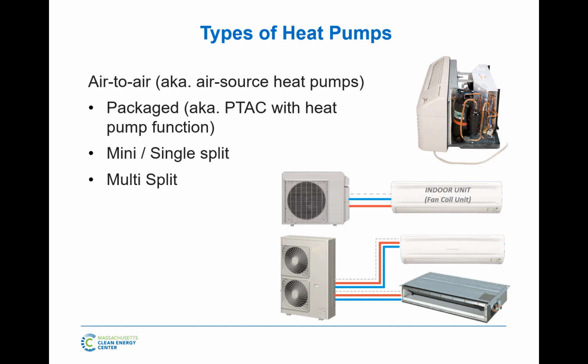But as a basic system, an air source heat pump does not come with electric resistance heat. The compressor itself that operates, the way that it generates heat is it moves heat from the outside to the inside, and you power it with electricity. There is some losses. It's not 100% efficient. So some of the power that goes into your compressor does get thrown in the refrigerant as some heat. So that helps you in heating. In cooling, it hurts you. You have to reject that extra heat. So you do get some help from electricity use of the compressor.